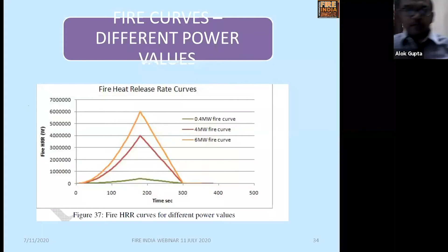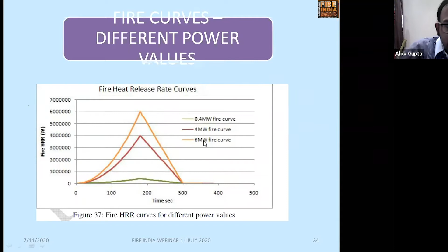This is the heat release rate curve, HRR curve, which around 300 seconds surpasses every type of fire, whether it's 0.4 megawatt, 4 megawatt, or 6 megawatt. But the smoke generated by these fires is more than around 200 ppm, which is generated by around a 6 megawatt fire.